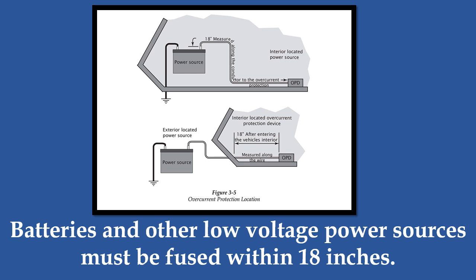In many cases, however, the overcurrent protection is installed outside on the A-frame near the battery. This provides the protection required throughout the length of the wire, including all wire on the interior up to the distribution panel.